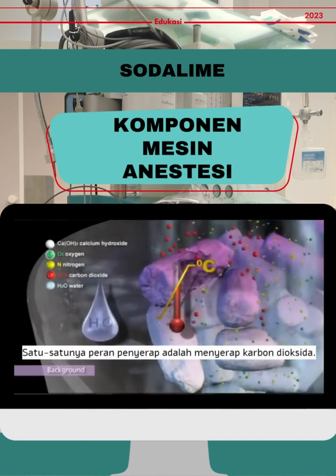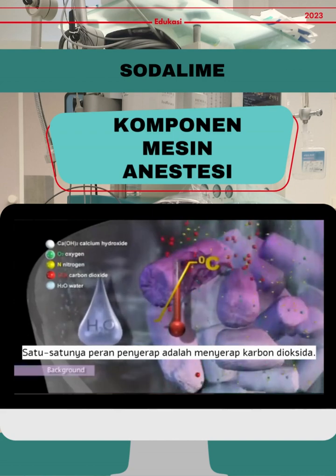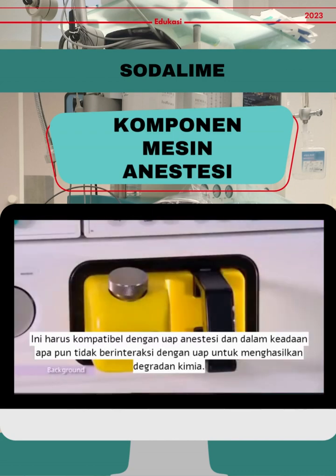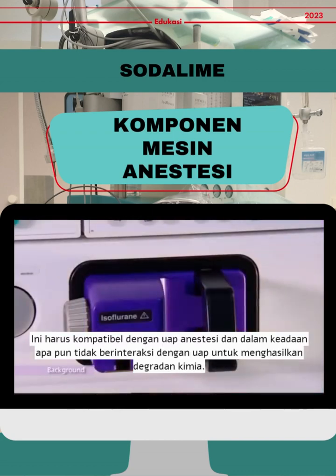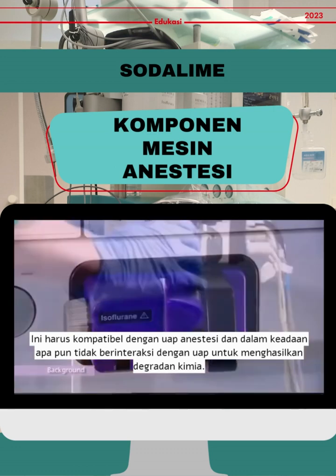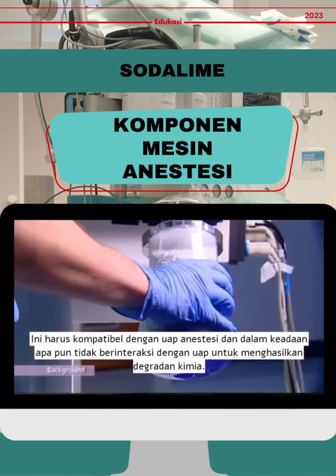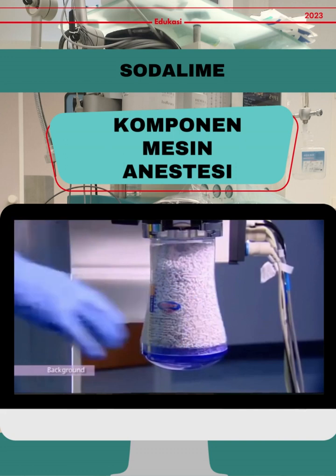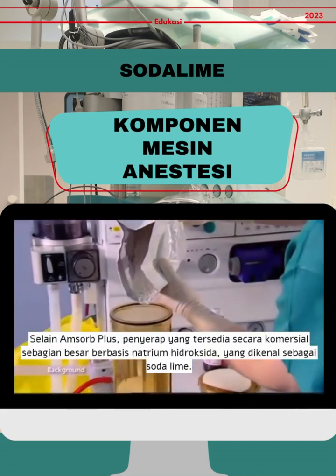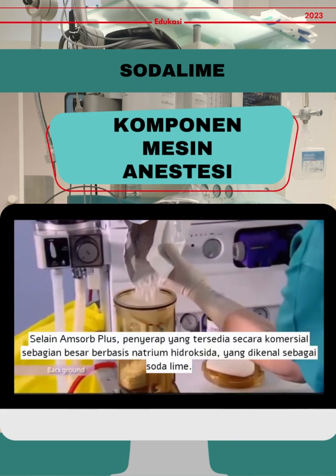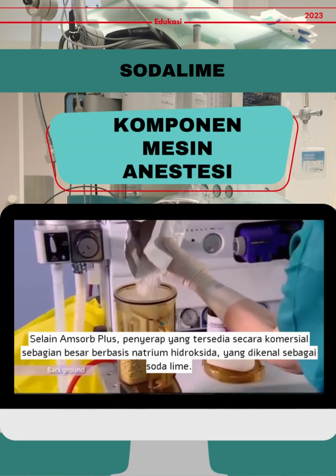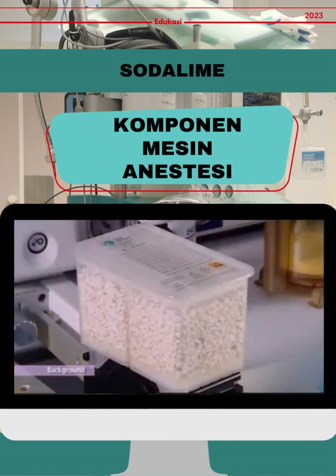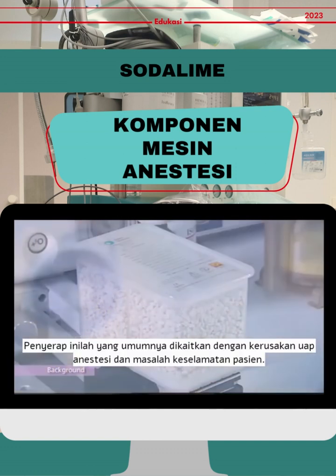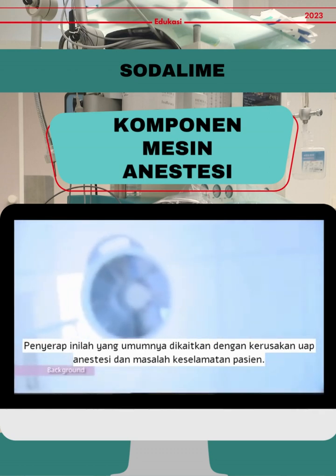The absorbent's only role is to absorb carbon dioxide. It should be compatible with the anesthetic vapor and under no circumstances interact with the vapor to produce chemical degradants. Other than Amsorb Plus, commercially available absorbents are mostly sodium hydroxide based, known as sodalimes. It's these absorbents that are commonly associated with breakdown of the anesthetic vapor and patient safety issues.